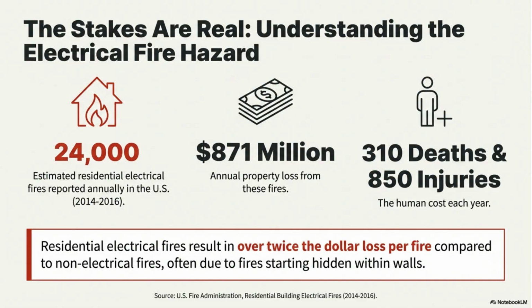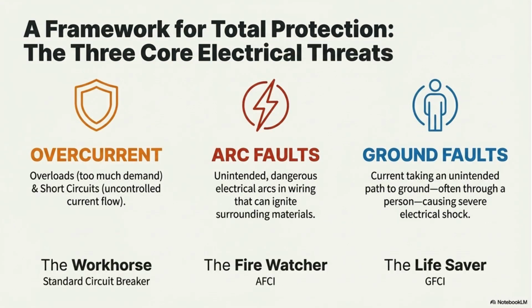Annually, these fires cause 24,000 incidents, resulting in $871 million in property loss and nearly 1,200 casualties. They often cause greater dollar loss per fire because they start hidden within walls. We must address three core electrical threats for total protection: overcurrent, arc faults, and ground faults. Standard circuit breakers manage overcurrent. AFCIs are the fire watchers, and GFCIs are the lifesavers.